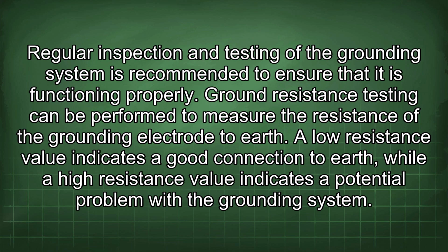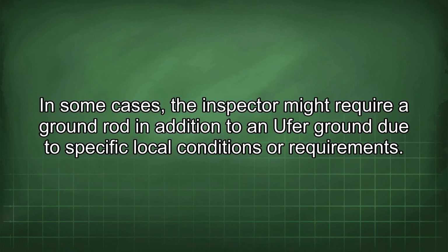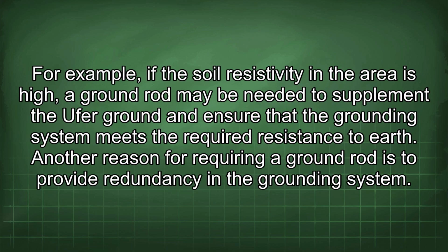A low resistance value indicates a good connection to earth, while a high resistance value indicates a potential problem with the grounding system. In some cases, the inspector might require a ground rod in addition to a Ufer ground due to specific local conditions or requirements. For example, if the soil resistivity in the area is high, a ground rod may be needed to supplement the Ufer ground and ensure that the grounding system meets the required resistance to earth.